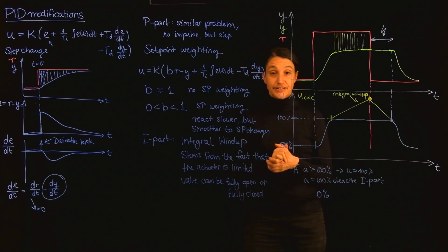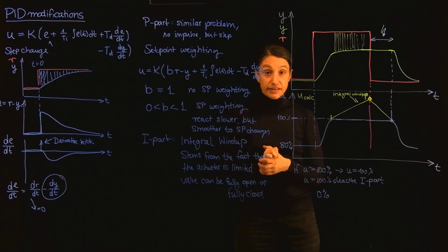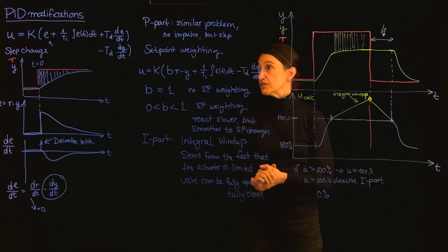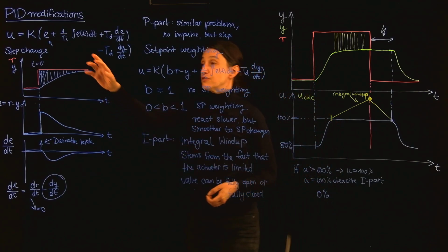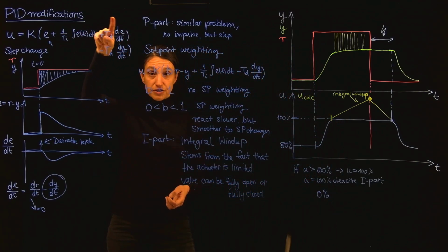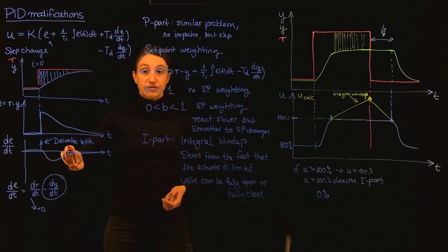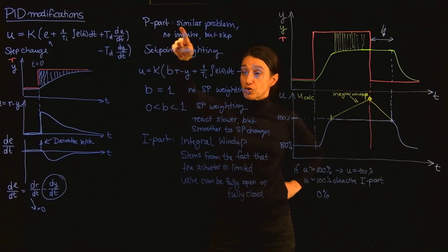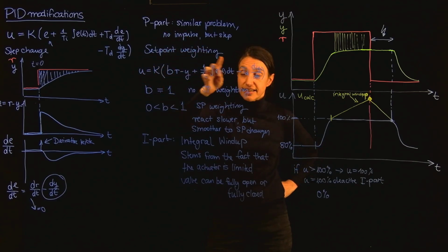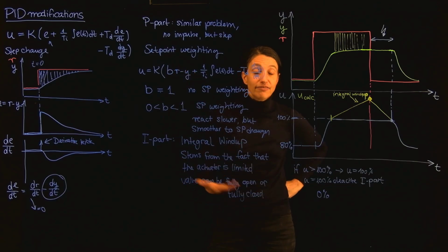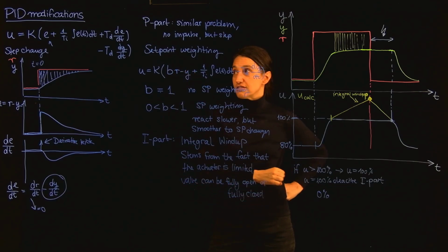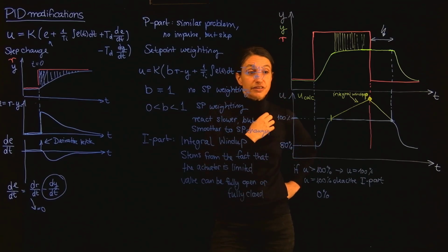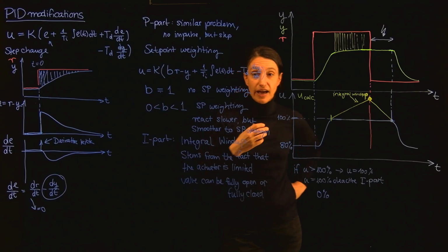Okay. So these are three very important modifications without which the PID controller will not work satisfactorily, especially for the process industry. So we first worked around with the derivative part and said, well, don't have the derivative kick. And then we said, actually, we have the similar problem with the proportional part. So we introduce set point weighting. And lastly, even our lovely integral part, which is otherwise doing the world for us, has a problem which is called integral wind-up, which we have to deal with.